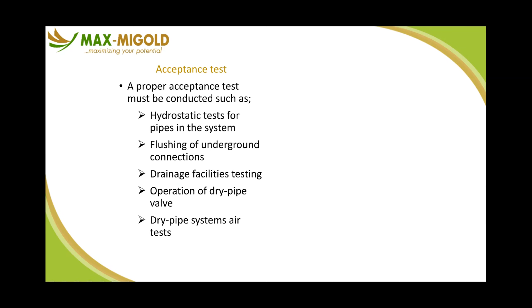It's about pressure testing. In a closed system, what goes in should come out when there's no leakage. So if I put a 4-bar or 6-bar pressure through the piping system, and the gauge is installed, I should be able to read it and confirm I still have my 4-bar or 6-bar intact in the pipe after a few days. Where that's not the case, there's leakage somewhere, or something is wrong. So you need to allow competent persons to do this.